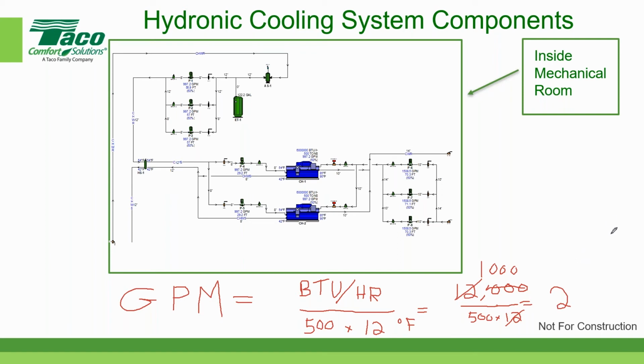How do you like that? Bingo, bango, bongo. And then Q equals 500 times GPM times delta T. 2 GPM per ton. Yep.